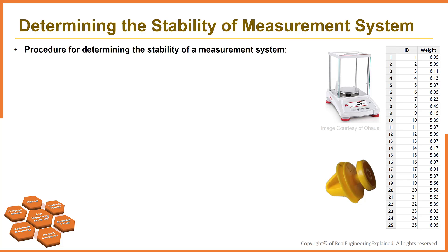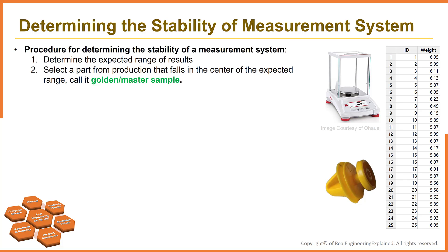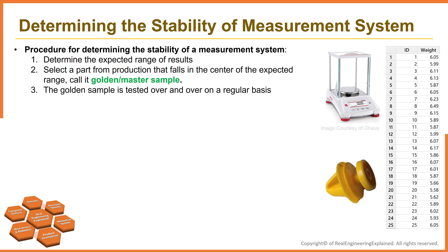The procedure for determining the stability of a measurement system using a control chart is as follows. Step 1: determine what the expected range of results is for a given measurement system — this is the range you would expect from production samples over time. Step 2: select a part from production that falls in the center of the expected range of results, and designate it as the master sample, golden sample, or gauge block for the stability analysis. Step 3: the master sample is tested repeatedly on a regular basis. How often should you measure? It depends on how often the measurement system is used. For example, if the measurement system is used on each shift, run the master sample once per shift.